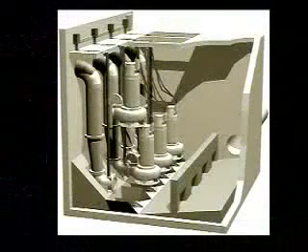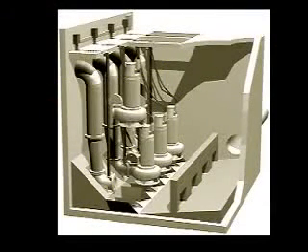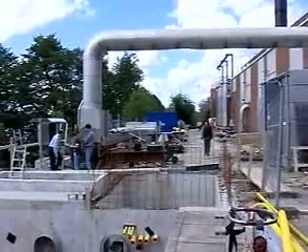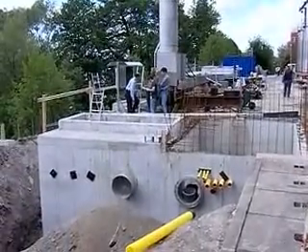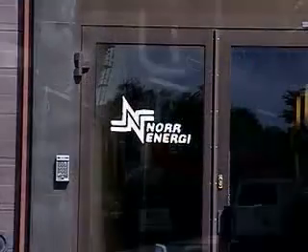Finally, this arrangement, which Flygt designates as type B2, has a straight baffle wall. Either the sump or the sewer is below the normal water level in the sump, or an open channel supplies the sump. In the absence of falling flow into the entrance, no intense entrainment of air takes place. Consequently, the inlet chamber can be greatly simplified because its only task is to distribute the flow evenly to the pumps.